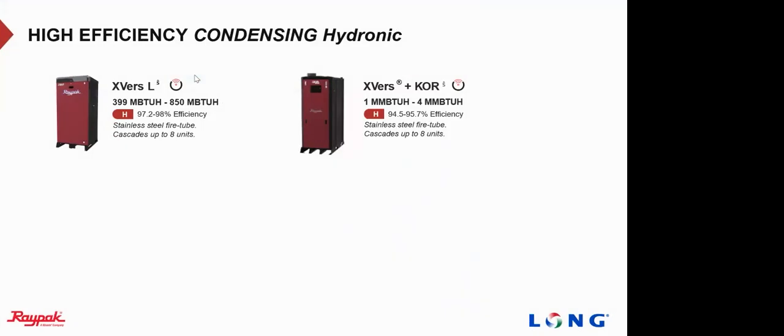So here are high efficiency condensing hydronic boilers. We have the Xvers with KOR, which I've already discussed. That's our 1 million to 4 million BTUs and all the sizes in between, fire tube. And then for your lighter commercial jobs, we have the Xvers L, which is also stainless steel fire tube, still high efficiency, same control that the Xvers KOR has. You can cascade up to 8 units. It's just a little bit smaller for your lighter commercial jobs, 400,000 to 850,000 BTUs.